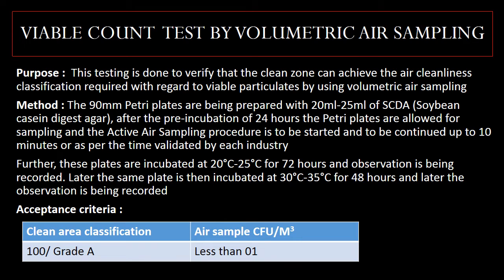The plates are then incubated at 20 to 25 degrees Celsius for 72 hours and observations are recorded. The same plates are subsequently incubated at 30 to 35 degrees Celsius for 48 hours and observations are recorded again. The acceptance criteria to comply with Grade A or Class 100 is less than one colony forming unit per one meter cube of air sampled.